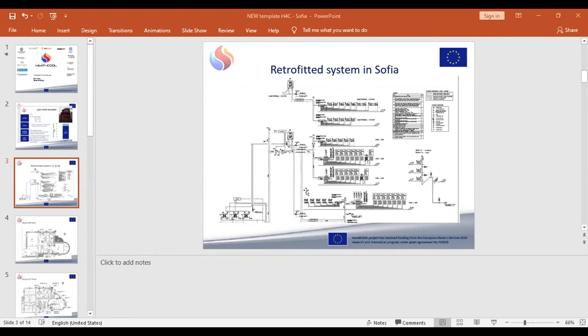So the heat pump unit is installed at elevation minus 2.40 meters, and 3 phase change material units, also called heat batteries, are installed in the vicinity of the heat pump unit. After the heat pump unit, 2 thermal loops are formed, one to the heat batteries and the other to the heating system. Circulation to the thermal circuit for the thermal batteries is performed via a circulation pump. Circulation to the heating circuit is achieved by means of a second circulation pump, but only one circulating pump works at a time. Priority is given to the heat pump charging the heat batteries through circulation pump 1. Because during the heating season, after the heat batteries have been charged, circulation pump 1 will shut off and circulation pump 2 is turned on.